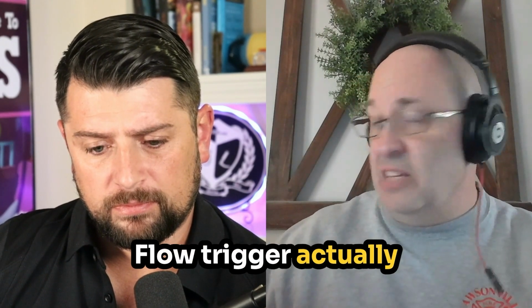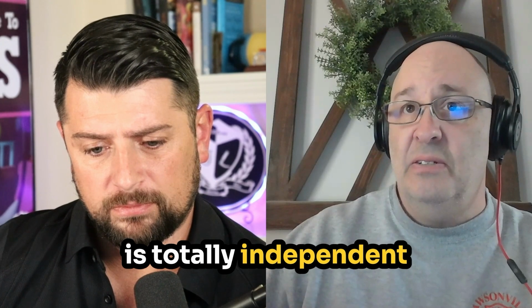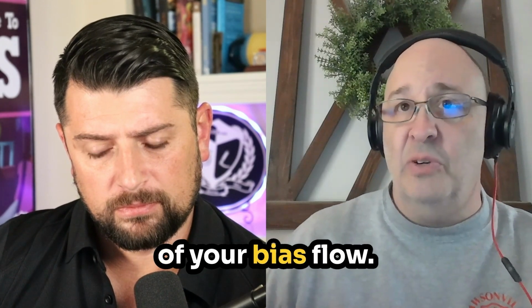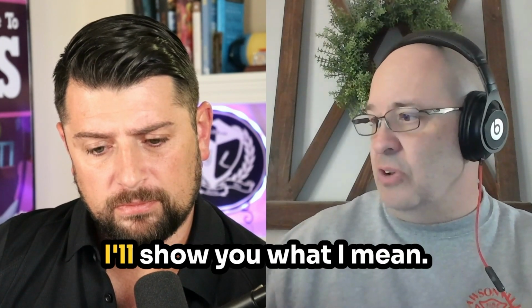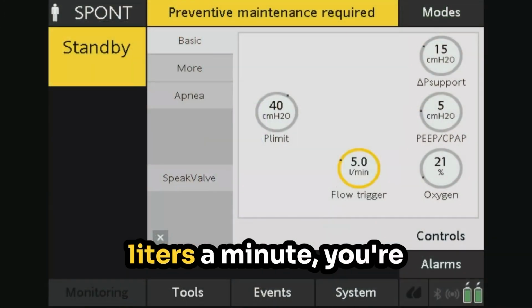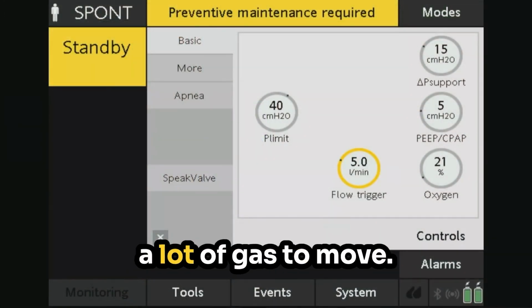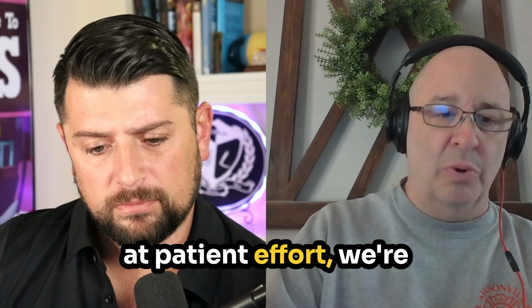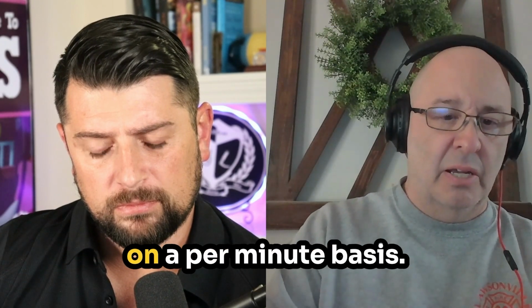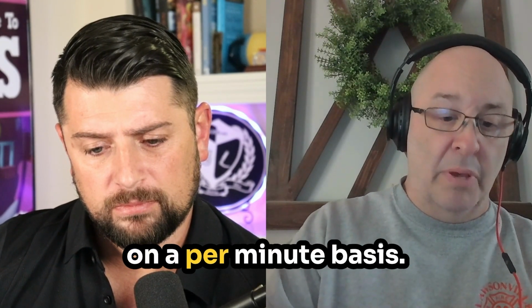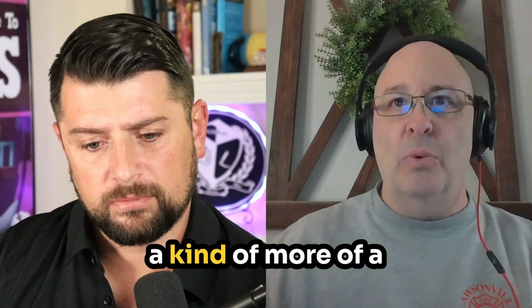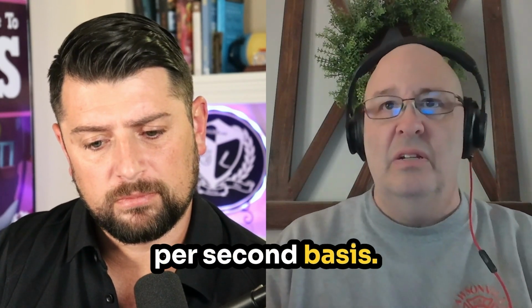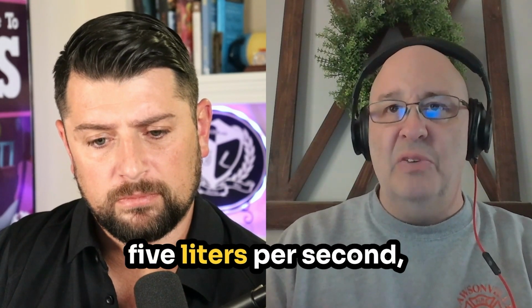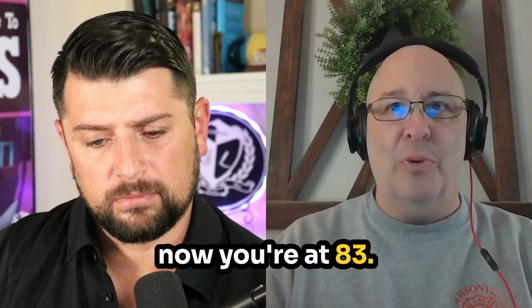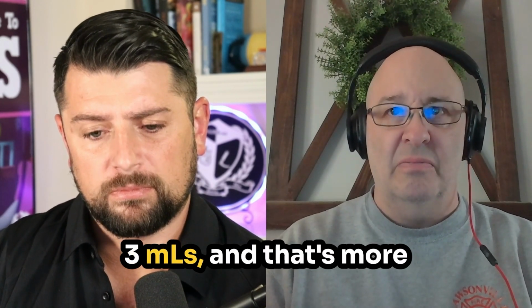But that's kind of where your bias flow comes into play. Flow trigger actually is totally independent of your bias flow. I'll show you what I mean. So if you look at 5 liters a minute, you're thinking, wow, that's a lot of gas to move. But when you're looking at patient effort, we're not really breathing on a per minute basis. We're breathing at more of a per second basis. So when you look at that 5 liters per minute per second, now you're at 83.3 mLs.